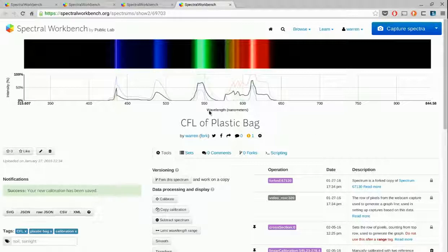And from here on out, you can copy this calibration to any other spectrum made shortly thereafter or with the same device. I would recommend that if you move your device or if it's just been a little while, say a few days or even an hour or two, it makes sense to do a new calibration, to run through this procedure by pointing it again at a compact fluorescent light to make sure that your spectrometer hasn't drifted.